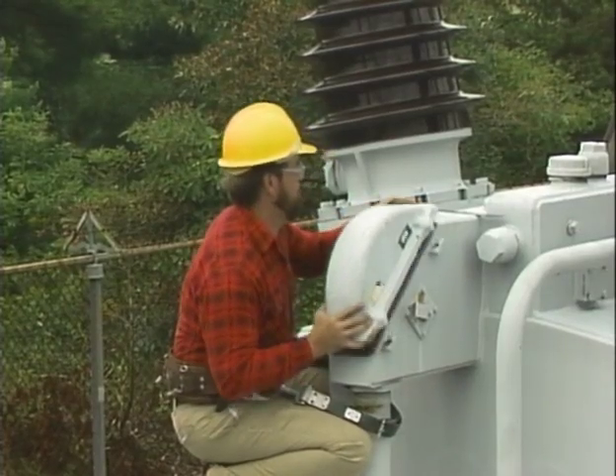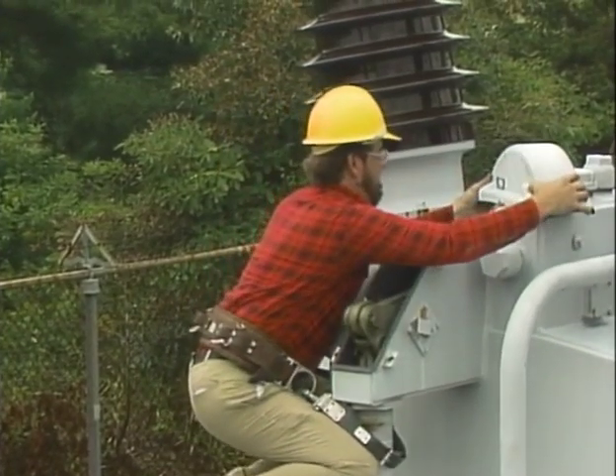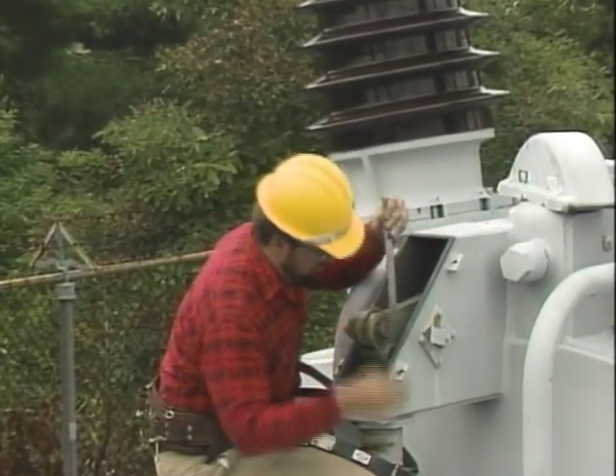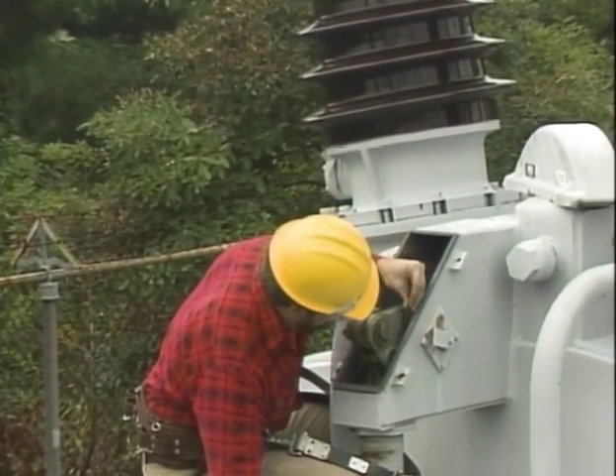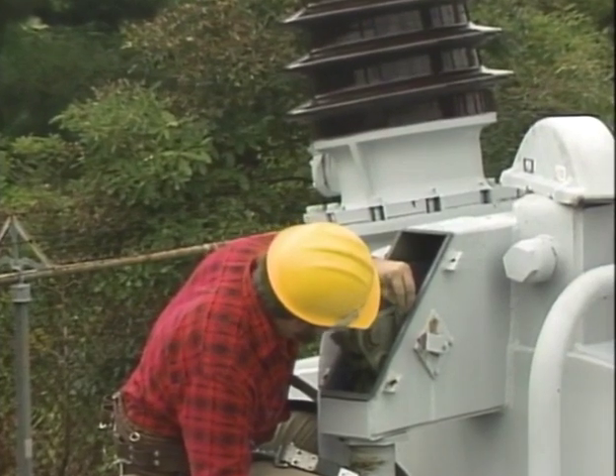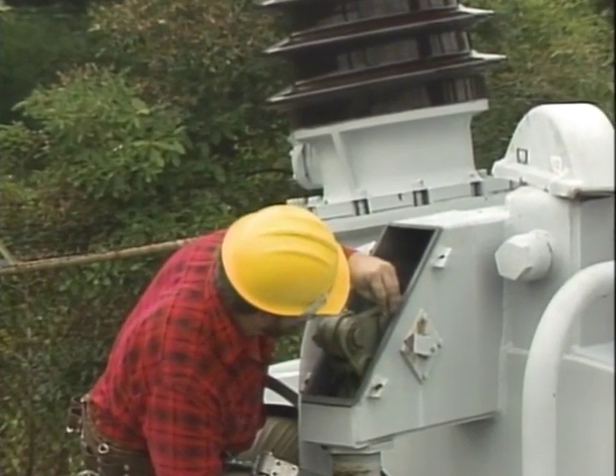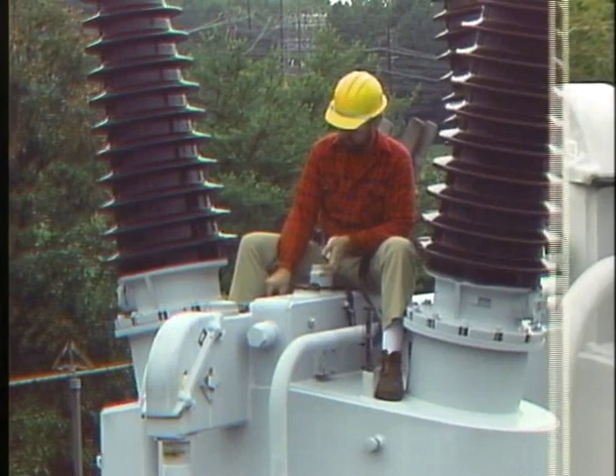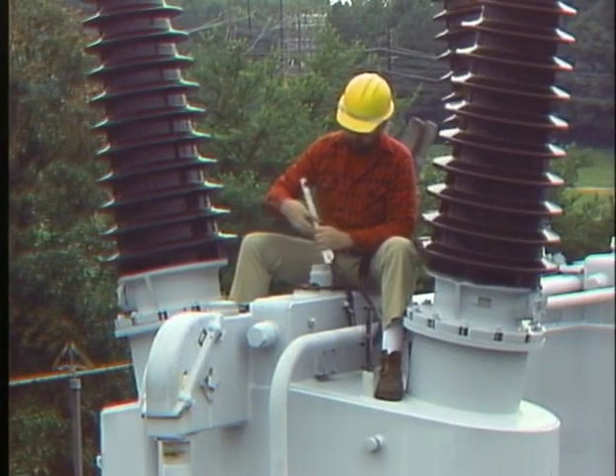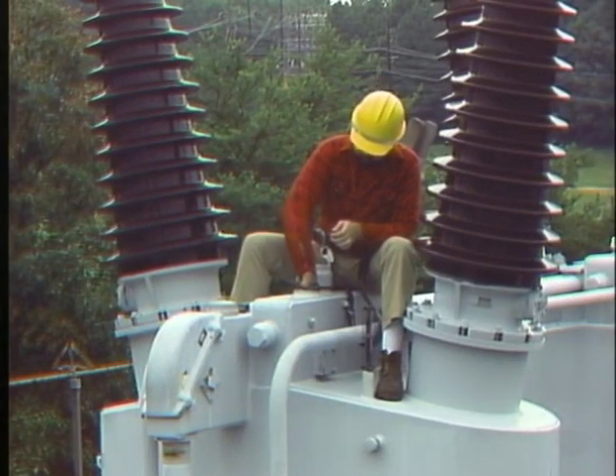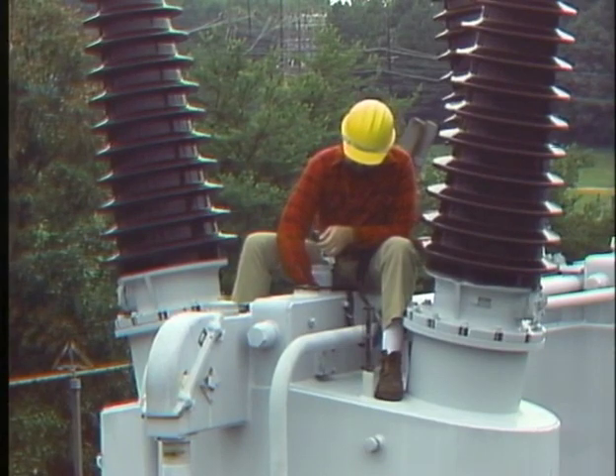The bell crank position is measured, typically when the breaker is closed. The bell crank is a mechanism that changes the direction of mechanical motion, such as changing the vertical motion of an operating rod to a horizontal motion. Operating rod position is also measured with the breaker closed to ensure that the rod is in the proper position.